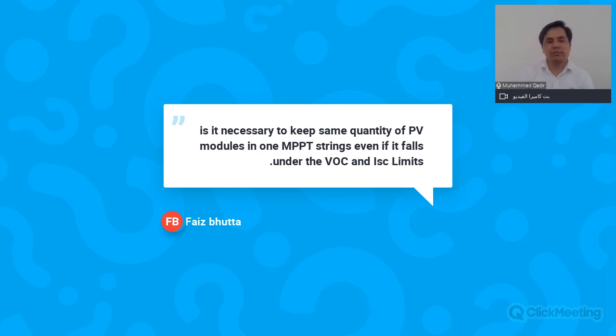Is it necessary to keep the same quantity of PV modules in one MPPT string even if it falls under the VOC and ISC limits?